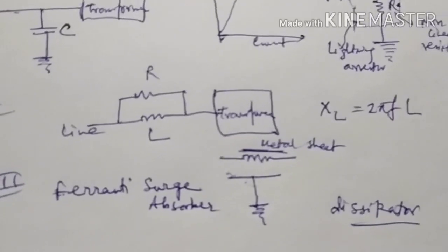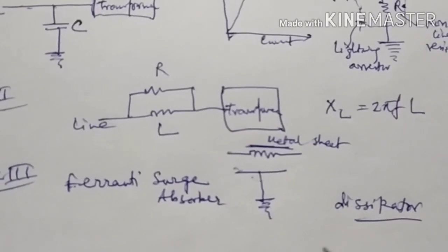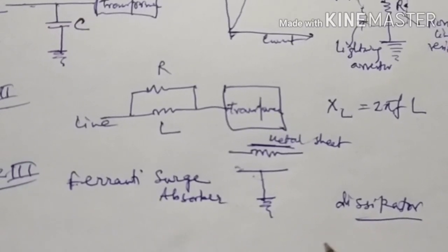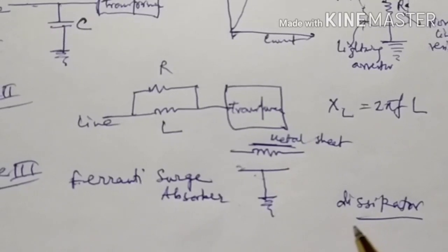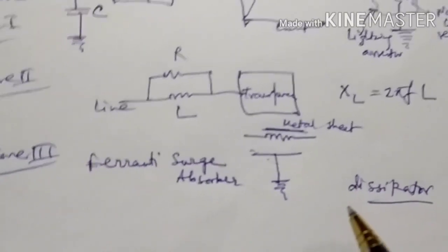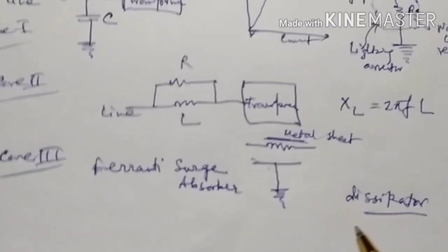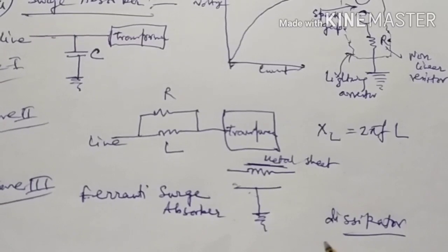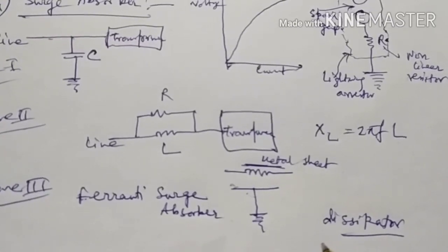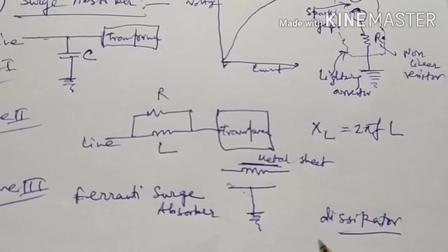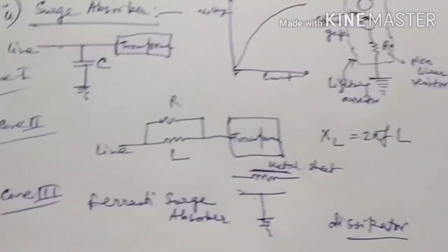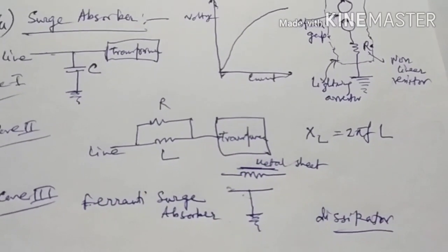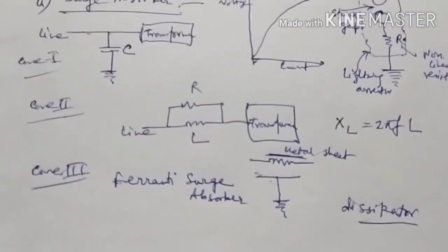While concluding the topic of protection against overvoltage, it is essential to discuss briefly the internal causes, that is arcing ground, which is often witnessed when the lines are long and operate at high voltage. Transients produced due to arcing ground are cumulative and produce severe oscillations of 3 or 4 times the normal voltage. As such, protection in a power system is very important and it can be prevented by earthing the neutral.